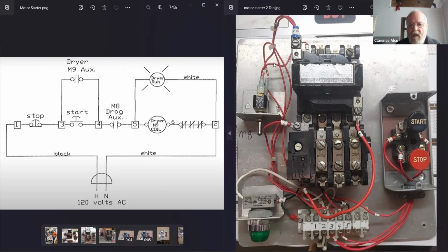So when we energize this coil M9, what should this set of contacts M9 do? Stay open or close? It should close, allowing current to flow through. So if that closes, now you've got current flowing through here. This is spring loaded. Now you can take your finger off of this thing. If you take your finger off, you'd think it's going to stop. No, it's not. This set of contacts is going to flow around there and keep that coil going.